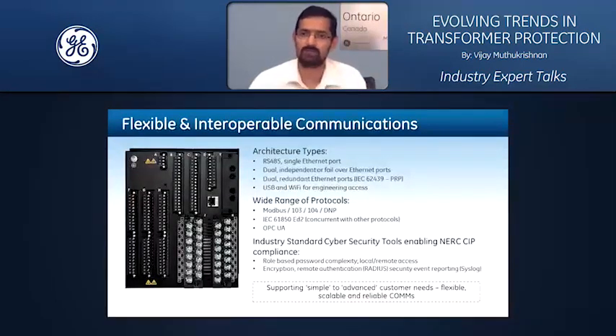Now going into protocols, once you have your base level of network architecture cleared up. Applications demand a variety of protocols. The simplest can be Modbus, all the way to the most recent Edition 2 of 61850, and the device should be able to support that. 845 is a 61850 Edition 2 compliant device. So it supports Modbus, 103, 104, DNP, and above all it also has OPC UA, which is very unique. Only the 845 series product line has OPC UA in the industry, and our 3 series product line also has OPC UA as part of the communication protocols offering. So you have the ability to meet your network needs and pull the data over any type of protocol you really need.